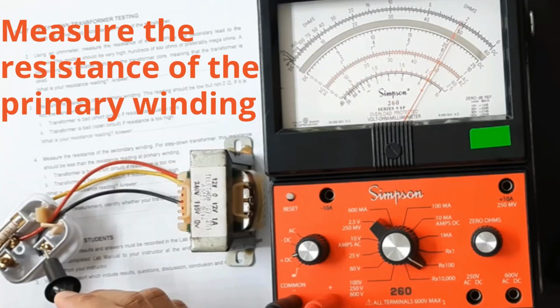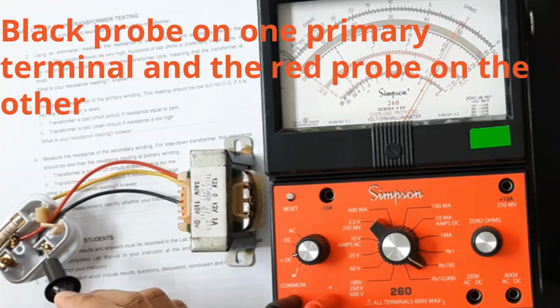To measure the resistance of the primary winding, first identify the two primary terminals. Place the black probe on one primary terminal and the red probe on the other. The multimeter should show a measurable resistance value, typically higher than the secondary, because the primary winding uses more turns of thinner wire.